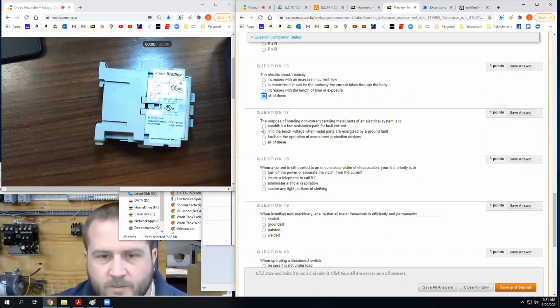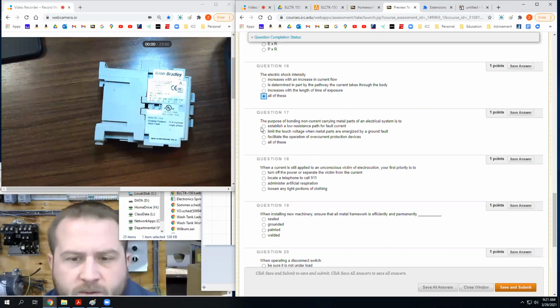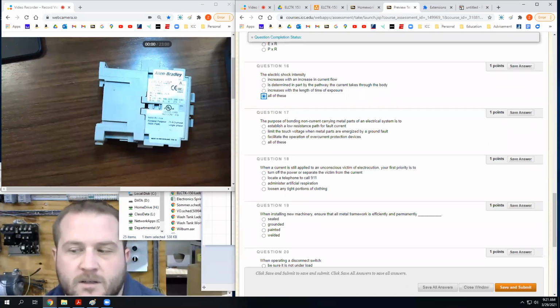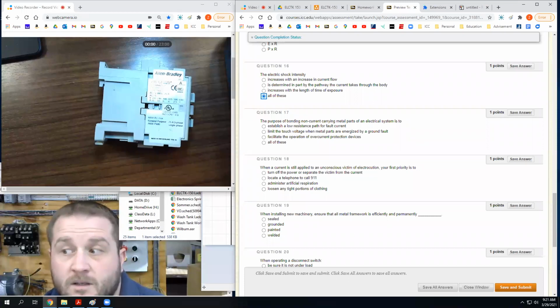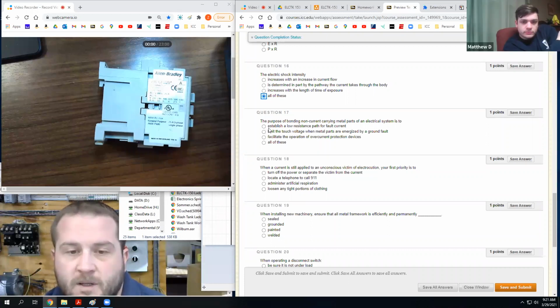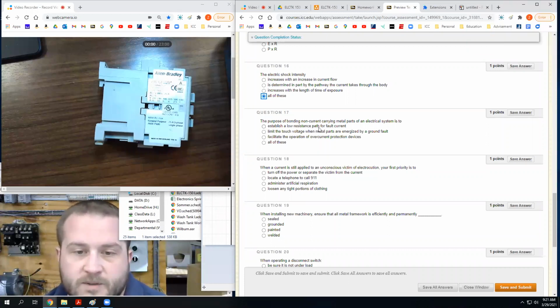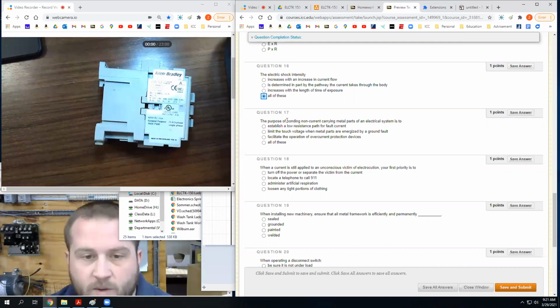The purpose of bonding non-current carrying metal parts of an electrical system is, I think, all of those, right? It does all of them. You want it to provide a low resistance path for fault current, because that's what's going to trip your fuse or your breaker or whatever's there to protect the system, protect the wire.